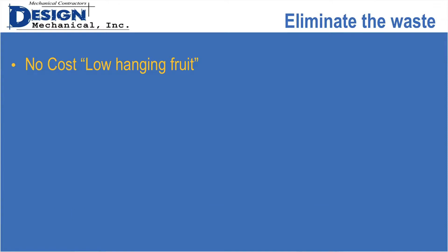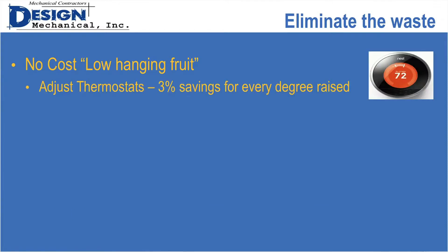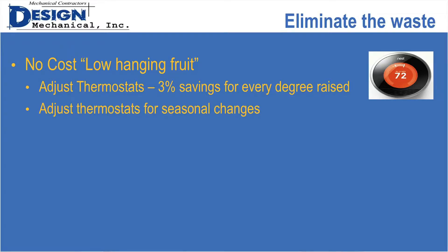Adjust the thermostat — Jimmy Carter figured this one out. Moving the thermostat up a degree saves 3% on energy associated with heating and cooling. Adjust thermostats for seasonal change. Some folks have just one thermostat set at 75 during cooling, but you don't want 75 during heating — when you change over to heating season, you might want to set it back to 68 or 70.